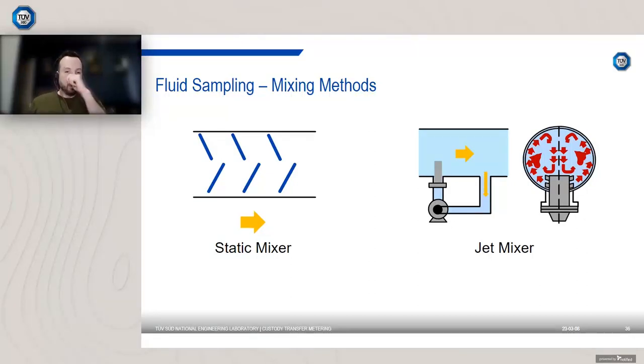So what are some mixing methods? Obviously you need to make sure the fluid is mixed. Common techniques are using static mixers, and static mixers provide distribution and dispersion of the flow. Some of them have one stage, some have multi-stage devices, or you can use something like a jet mixer, where you've got a dedicated jet mixing pump. The advantage of a jet mixer is usually you're bypassing the flow, so you're not introducing a pressure drop into the line. So both have their pros and cons.